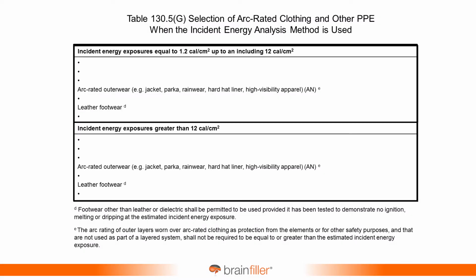Where we have that is right here. This is for the incident energy analysis 130.5G, and there's a whole lot more than what I'm showing right here. But this table is broken up into the PPE up through 12 calories per square centimeter, and then at the bottom, greater than 12 calories.